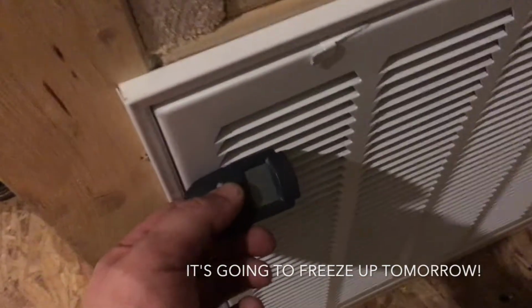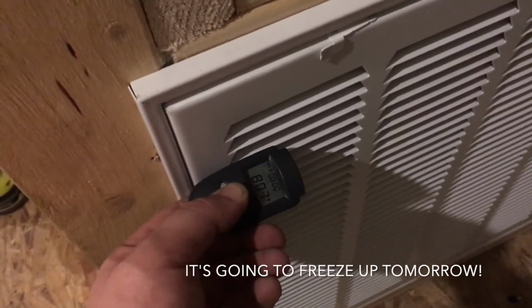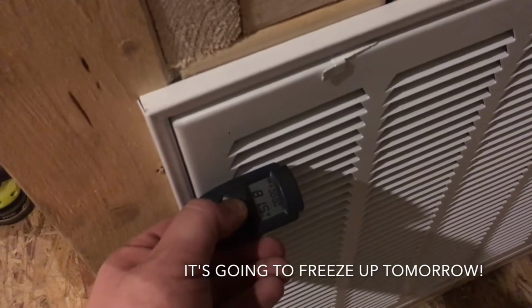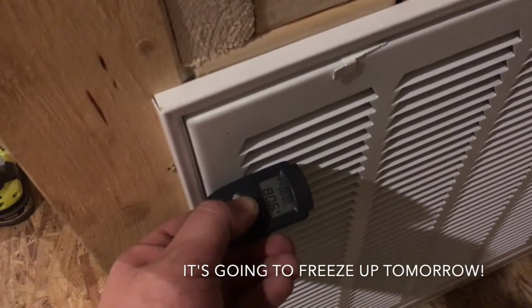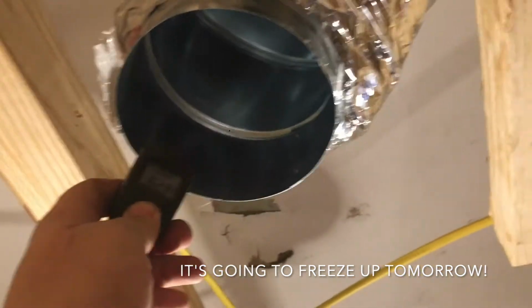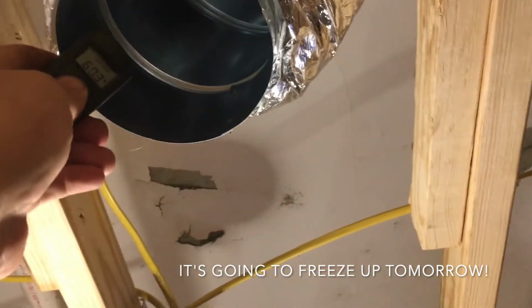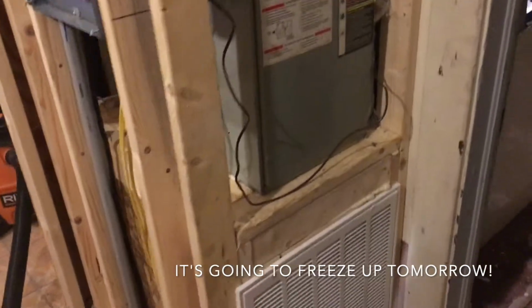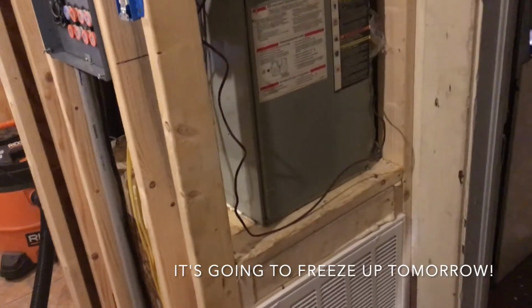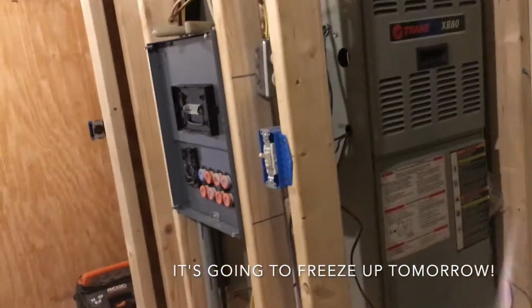And if I check delta T, we've got about 80 degree air coming in, 81. Yeah, about 80 to 81 degree air coming in. And we've got 59, 60 degree air coming out. So that's about 20 degrees of delta T. That's very good. Delta T should be between 18 and 21, so 20 is a great number.